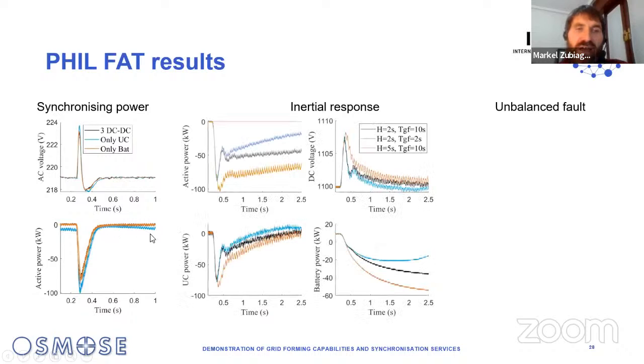So when the grid changes its angle, the grid-forming control reacts by smoothing the frequency and giving this power. The next results are related to the inertial response and the answer regarding the RoCoF. Here we can see there are different setups regarding the transient grid forming. So the inertial response, the first surge or first peak, is really similar and more related to the inertia, while the duration of the injected active power is more related to the transient grid forming settings or filtering constant.